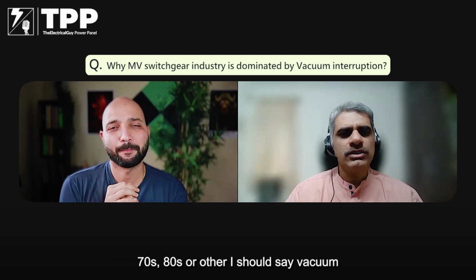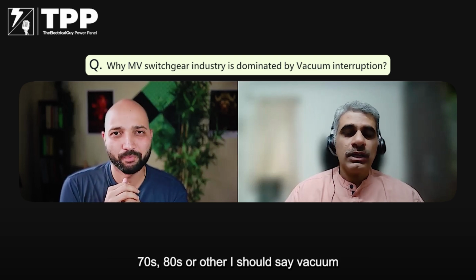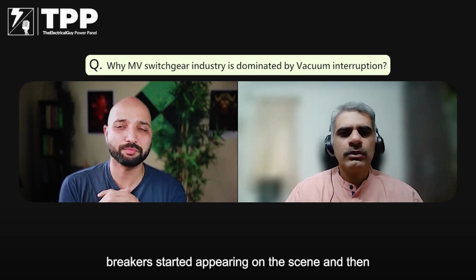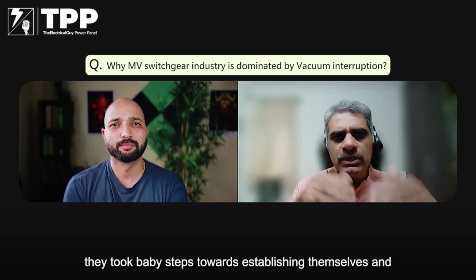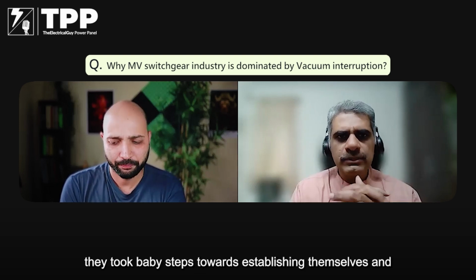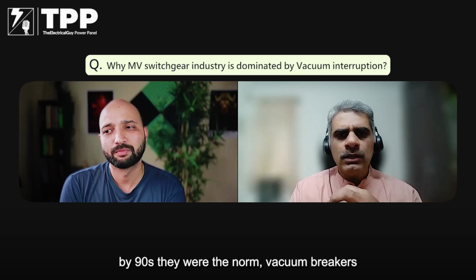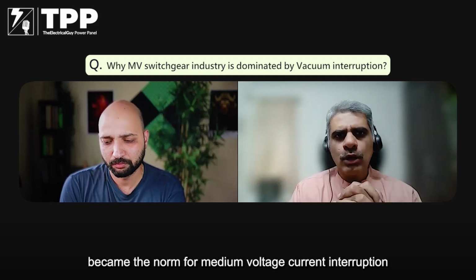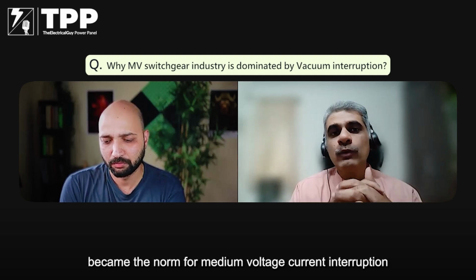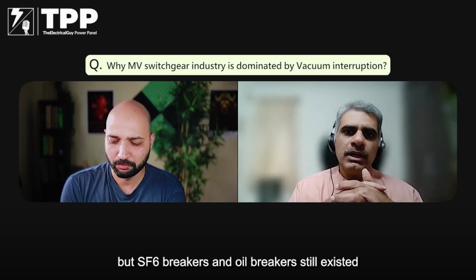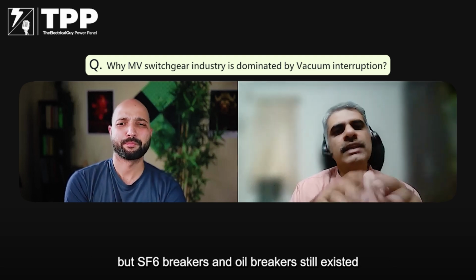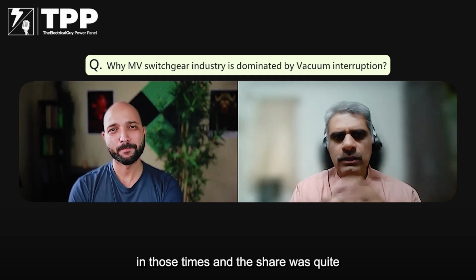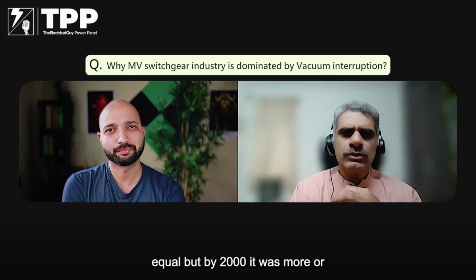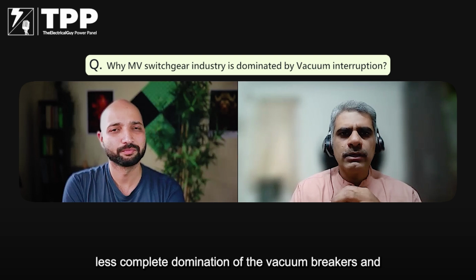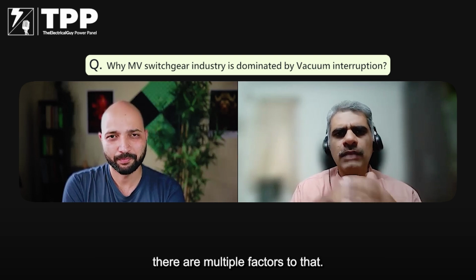Okay. So slightly I'll go back to the history. Vacuum breakers started appearing on the scene in the 70s and 80s, and then they took baby steps towards establishing themselves. By the 90s, they were the norm. Vacuum breakers became the norm for medium voltage current interruption. But SF6 breakers and oil breakers still existed in those times, and the share was quite equal. But by 2000, it was more or less complete domination of the vacuum breakers, and there are multiple factors to that.